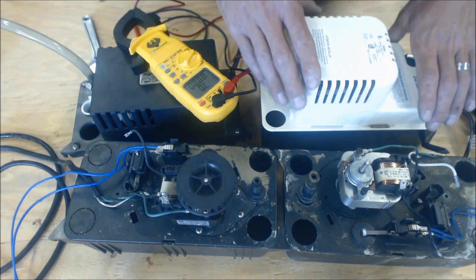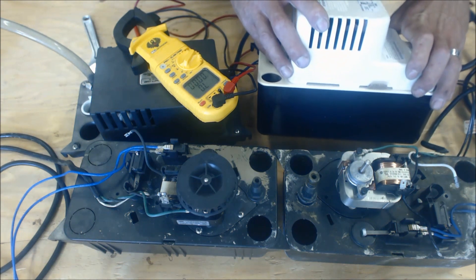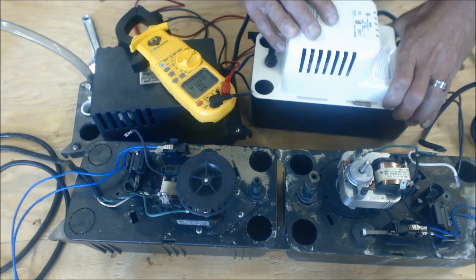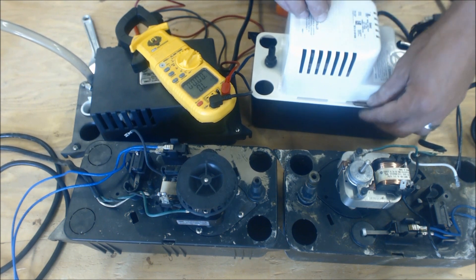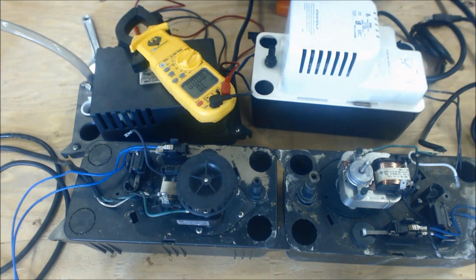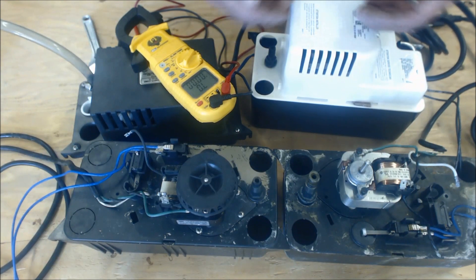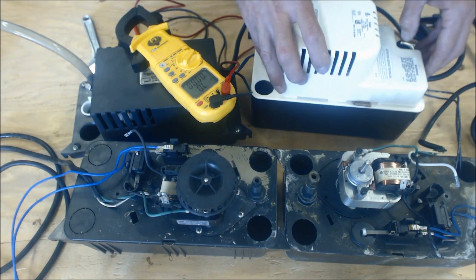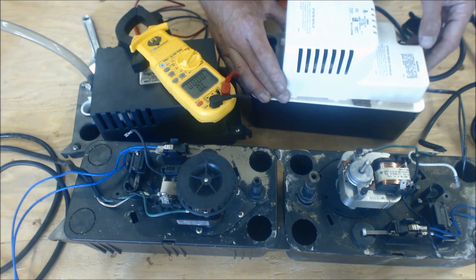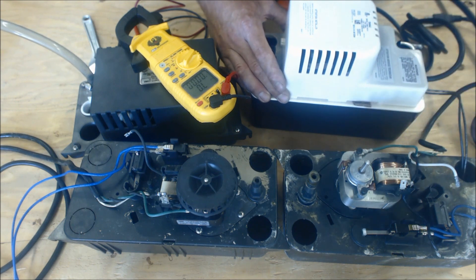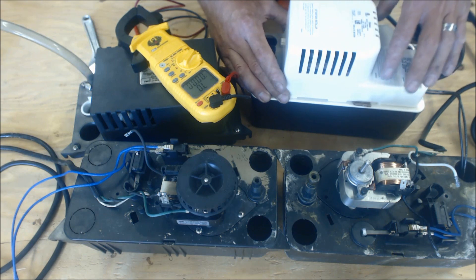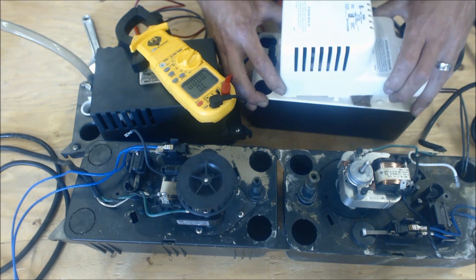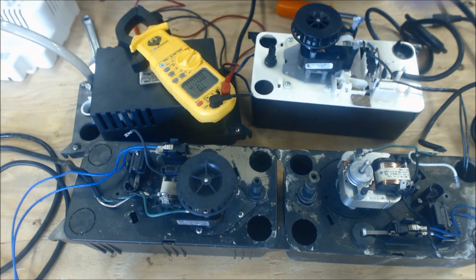If you are installing this type of condensate pump, right in this tab will not allow the condensate pump to turn on. So even if you fill this thing up with water and it's plugged in, it's not going to turn the condensate pump on, it's just going to let water overflow. It's actually holding the switch down. So what you need to do is you can actually just pull that out and you're fine. But just for us to take a look at the inside, we can just remove this screw right here, slide this forward and open it up.